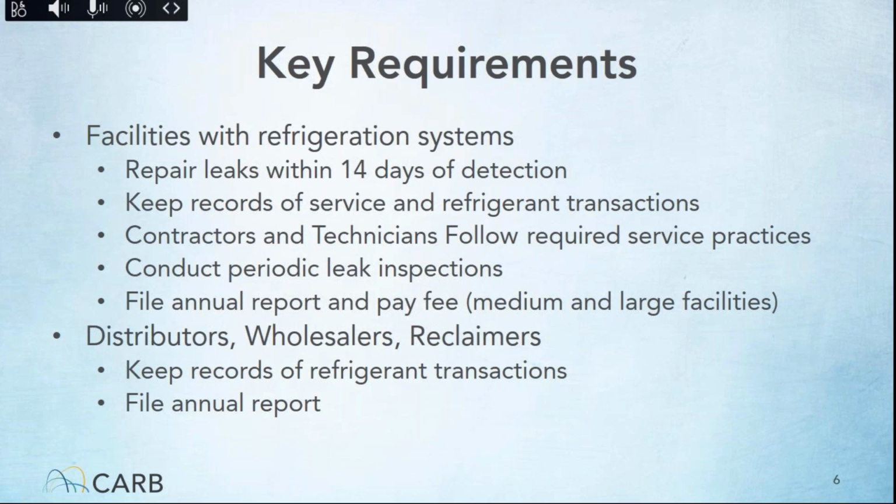If the two 30-pound systems are somewhat connected, even if it's an on and off valve, then those would be two 60-pound systems. I've never heard of a single system being able to handle two refrigerants, so at minimum it looks like in this scenario you have two 60-pound systems and possibly four 30-pound systems, depending on the circuit you have there. Feel free to reach out to us later on if you have any questions, and we can go through that specifically.